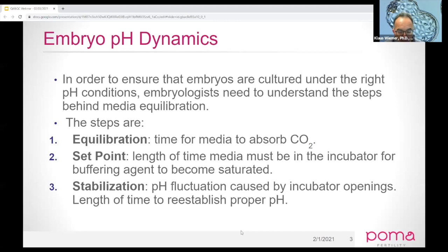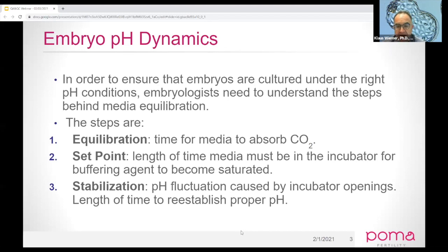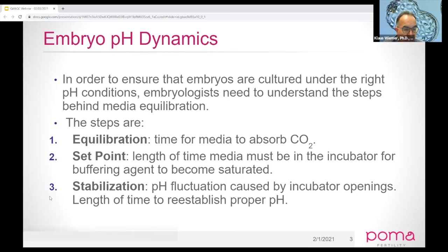Equilibration is the amount of time that culture media takes to absorb CO2. The set point is the amount of time that once the media starts absorbing CO2, the buffer becomes fully saturated. Stabilization is what we're all really looking for — those are fluctuations that occur in media once the embryo has become fully equilibrated.